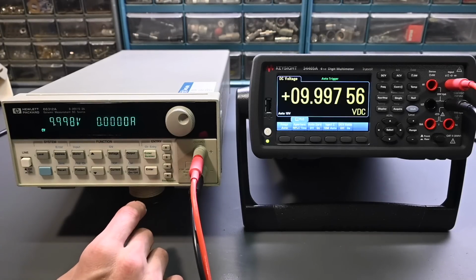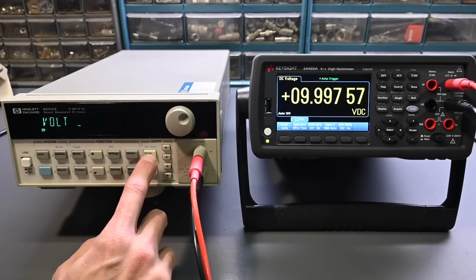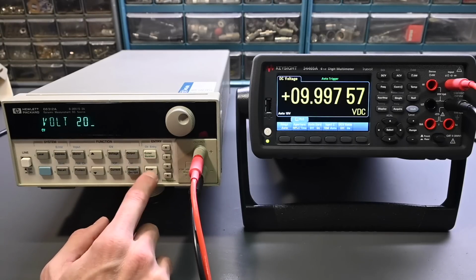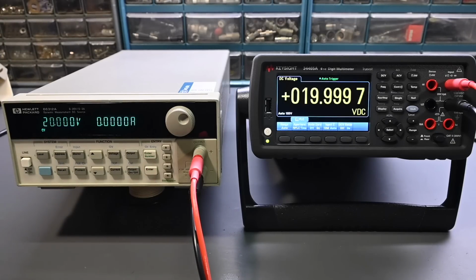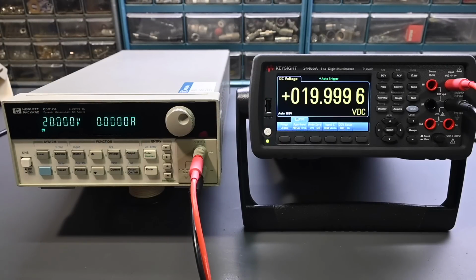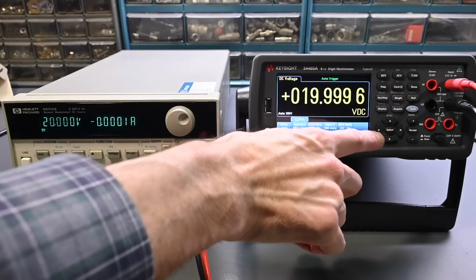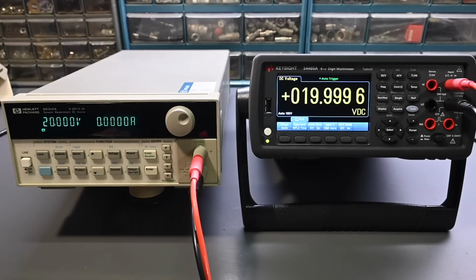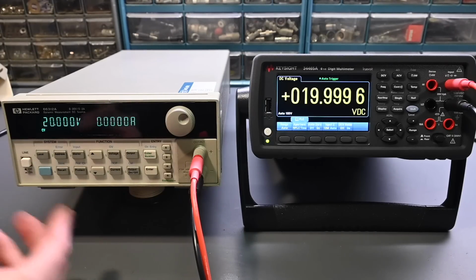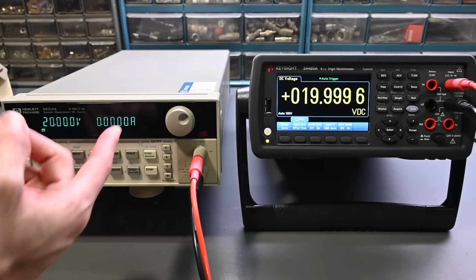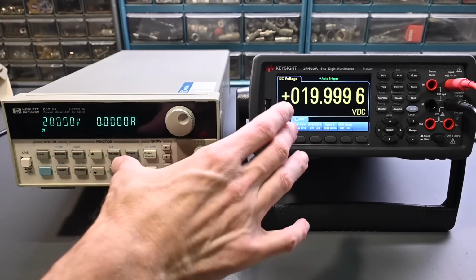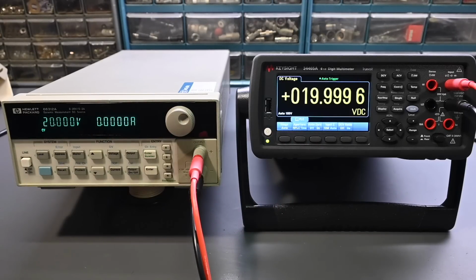And let's just go to the full output. So go voltage, enter number, try 20, enter, so 20 volts. And yeah, sitting right at 20 volts there, no problems with that. Let's look at the current measurement ability. So I don't need to connect it to an electronic load. I can just connect it in the current measuring function on the digital multimeter. Yes, that puts a direct short on the power supply, but it'll go into constant current mode, and then we'll still be able to use the readings and compare the current measurements.